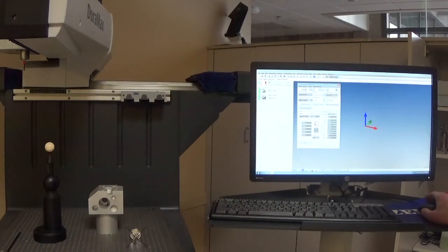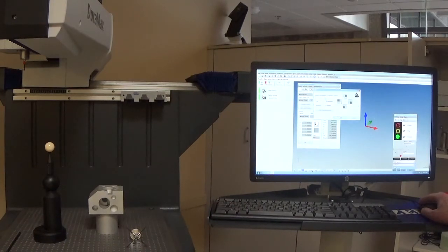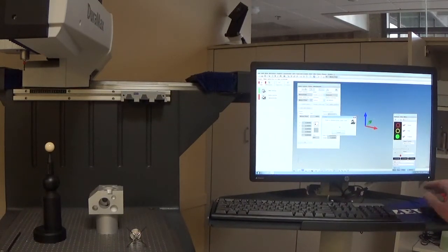So we have our master probe in, we have our qualification sphere attached and tight so it doesn't move, and now we need to qualify that master probe. So we click on the reference sphere position, and we need to select the orientation of the reference sphere, and we can just click OK. And then we have another information window that we can click OK. And now we need to probe in the direction of the sphere with the master probe.